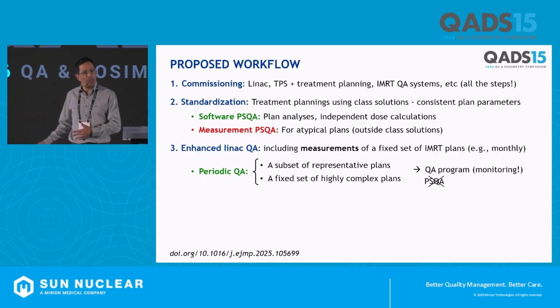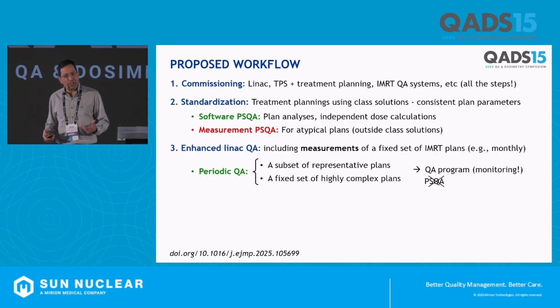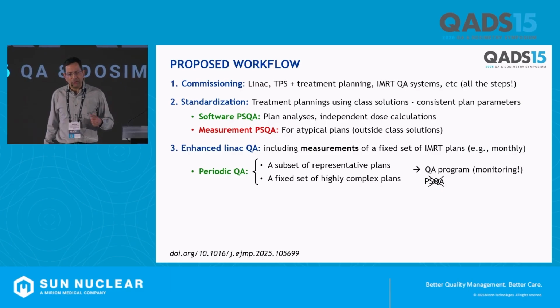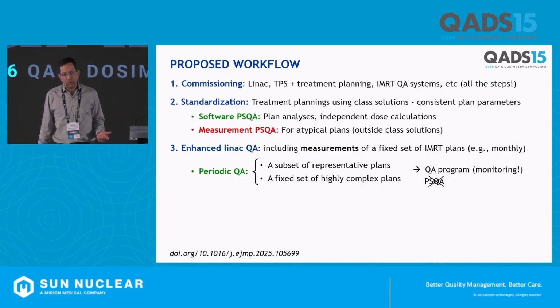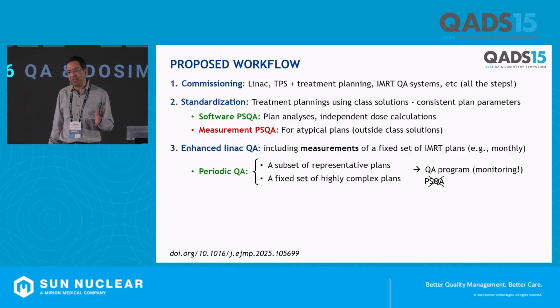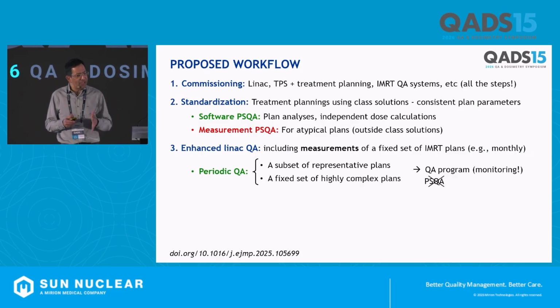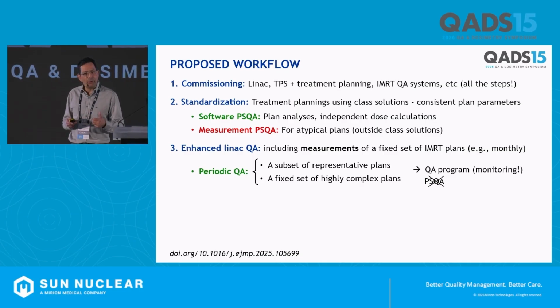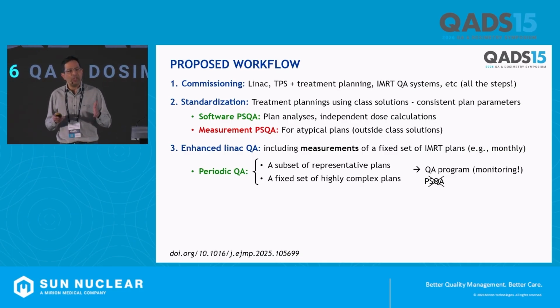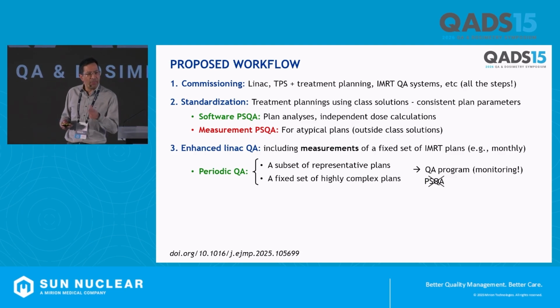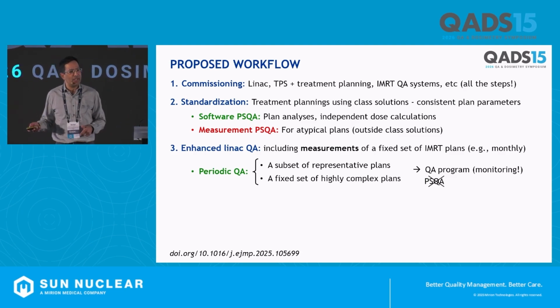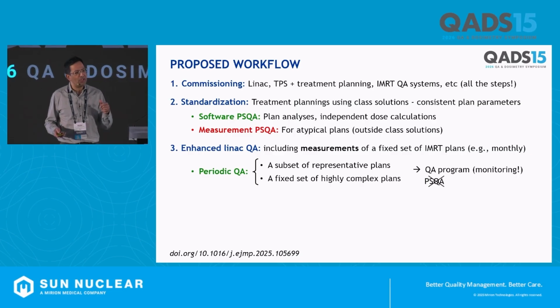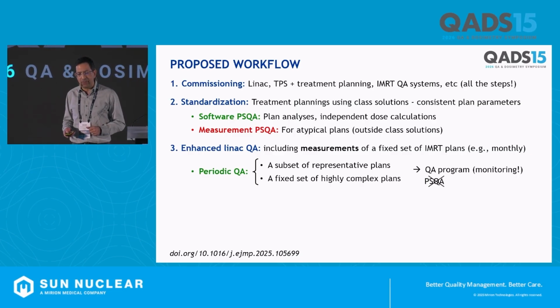Then, if you do less PSQA, it means that machine QA gets more important, so you need an enhanced LINAC QA. How can you do that? For instance, by including measurements of a fixed set of IMRT plans every 2 weeks or monthly, meaning that you evaluate a couple of representative plans or a fixed set of highly complex plans that allow you to verify that everything is in control, that everything is stable. But that's not PSQA. That's no longer PSQA. That's part of your QA program. That's machine QA, even if you're using the same system.